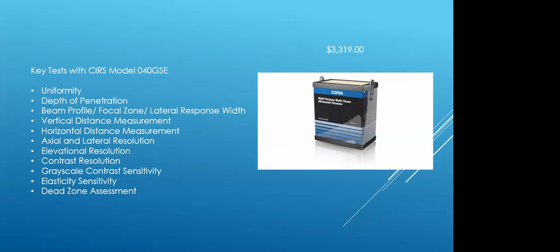or materials. Now, if you open up that phantom, basically what it does is it gives you different materials which are known in terms of being characterized. So when you measure, you're simply saying, I want to get the same output every time that I use the ultrasound machine, and anybody can use that and verify, and you also have a record of measurement over time.